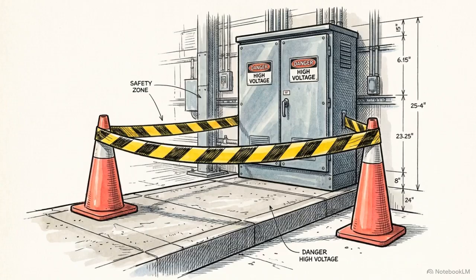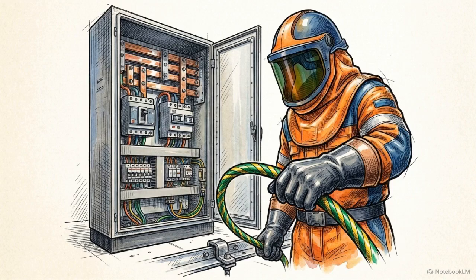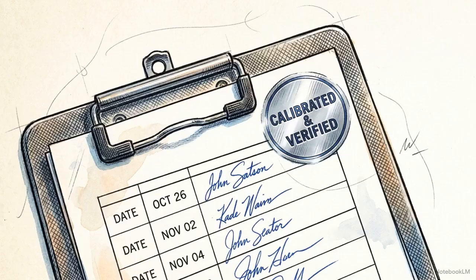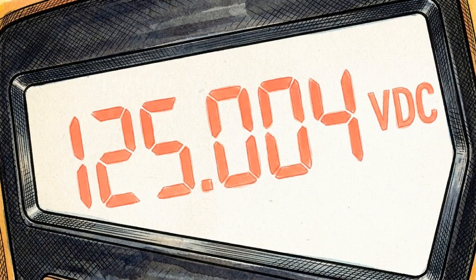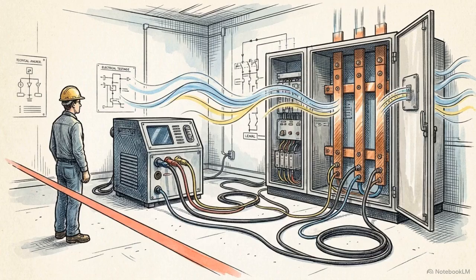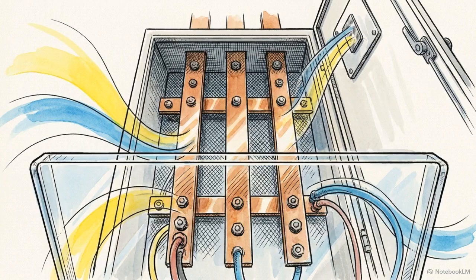Testing zones require rigid environmental boundaries. The area is isolated with warning tape, proper grounding connections are verified, and all personnel must wear ARC-rated personal protective equipment. No test leads touch a terminal until calibration certificates for all primary test equipment are verified. The instruments measuring these exact tolerances must provide absolute accuracy. Strict procedural discipline and precise instrument calibration ensure the engineer remains physically separated from live DC circuits while the board is under test.